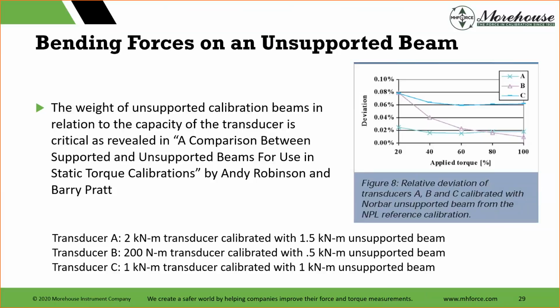And you can see the applied torque, and you can see the deviations. So what are they doing? Their relative deviation of transducers A, B, and C calibrated with Norbar unsupported beam, and they use the NPL reference, the machine that's at Morehouse right now they used. When NPL had it, the machine was good to 18.3 parts per million. A little bit better than us. We have to account for additional errors with different uncertainty components with accreditation. So they did this, and here's the data.